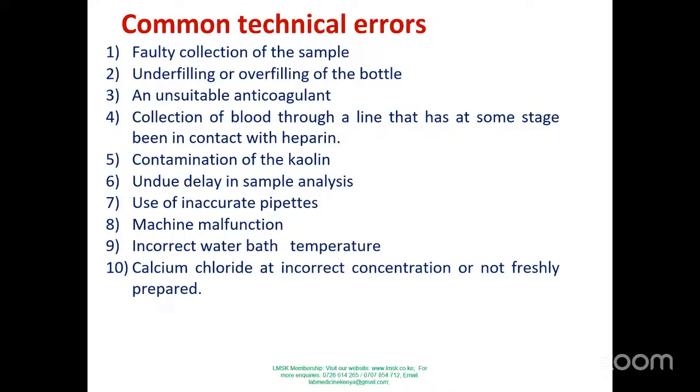Maybe the machine has broken down, so you need to do the necessary requirement, like contacting the provider or rather the vendor to come and repair the machine. And once that is done, again, you do your QC check just to ensure that the machine is functioning properly after repair. Incorrect water bath temperature.